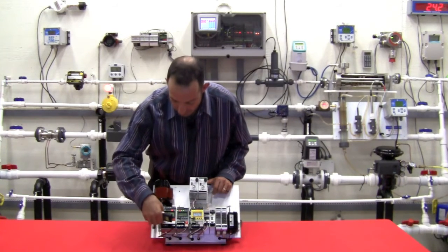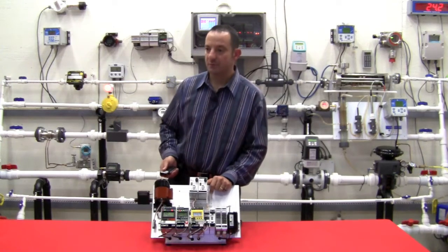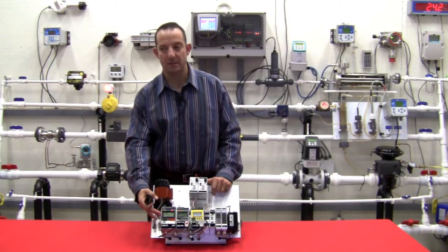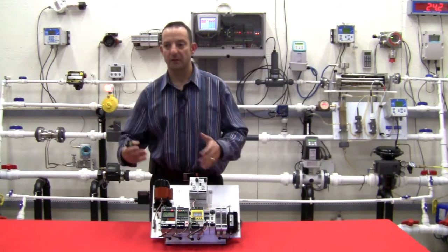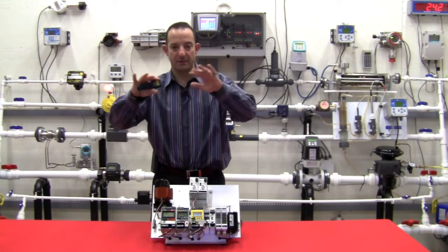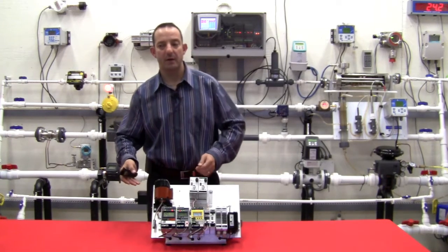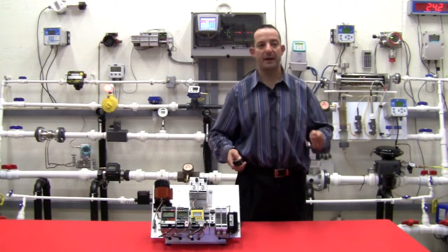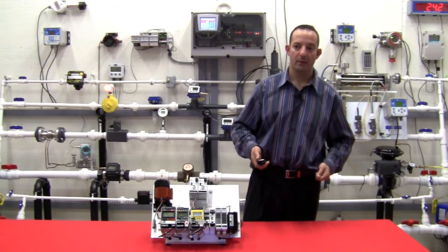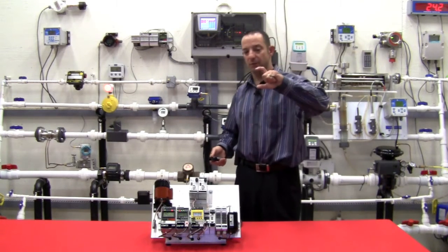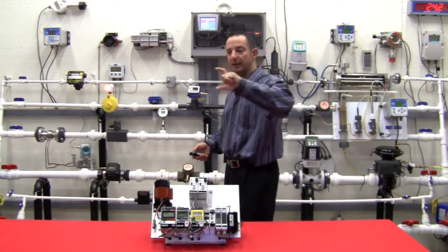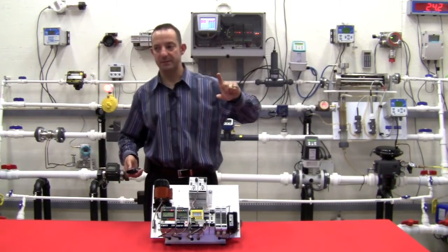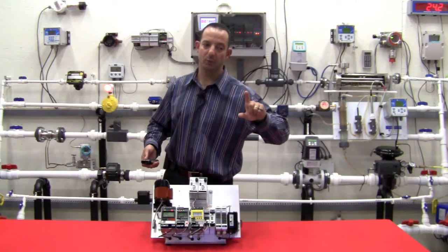We are PC programmable. So the HIM comes with a free piece of software and a cable, and you set it up with your PC using a software package that's got the look and the feel of the other Moore Industries software packages, everything on one screen. Compared with the Rosemount Tri-Loop, where you have to go in and configure it with a HART handheld communicator over the current loop. And we know that HART handheld communicator is only this big, the display is only this big, and it only has a few lines on the display, and the menu structure is a lot more cumbersome than that of a PC program. Our software and cable is free of charge.